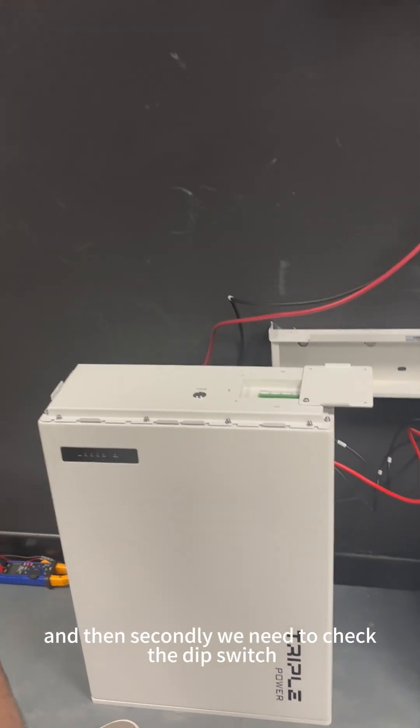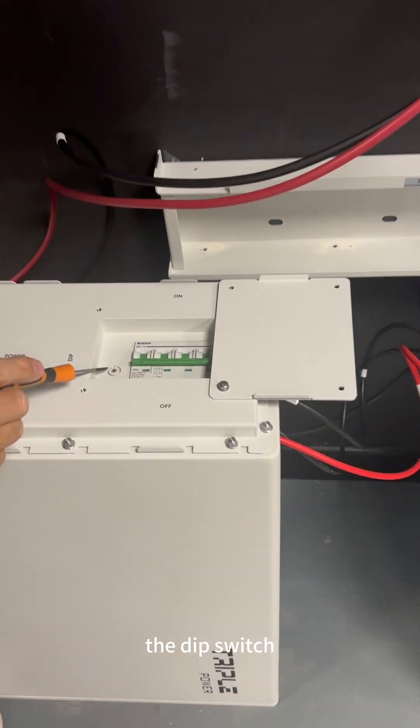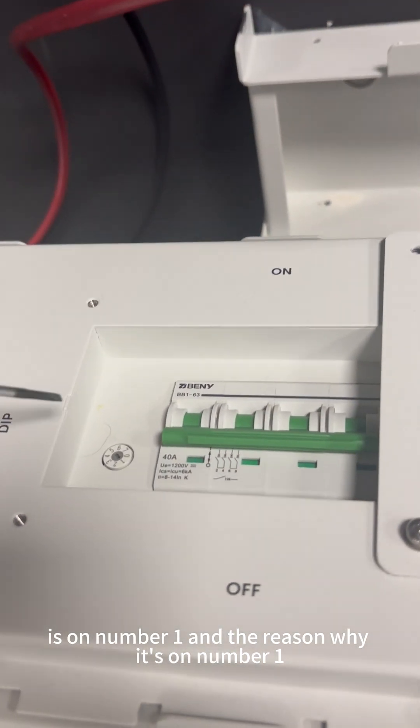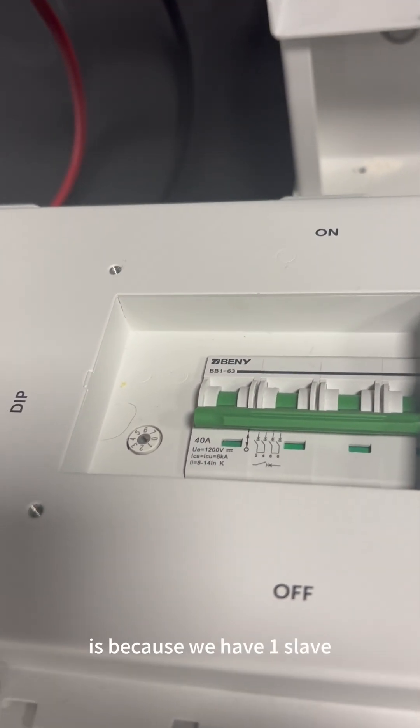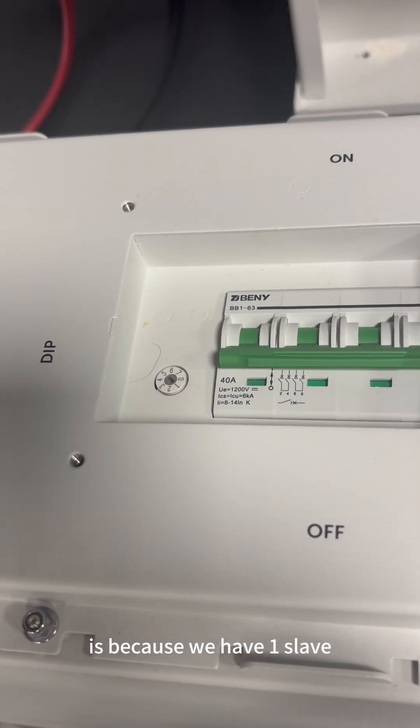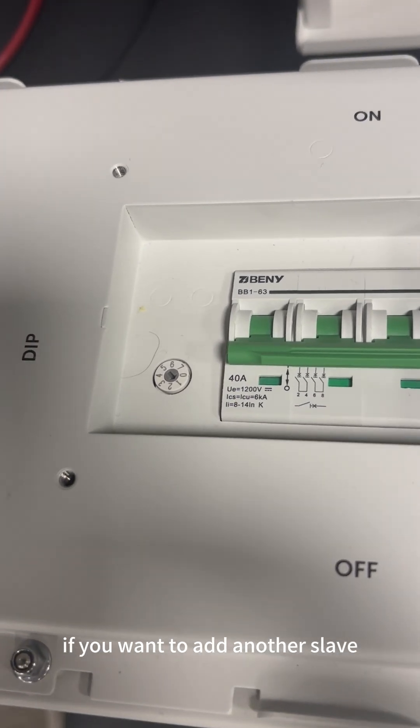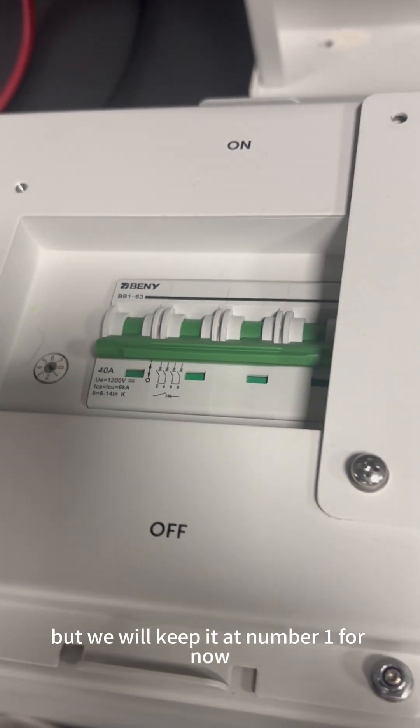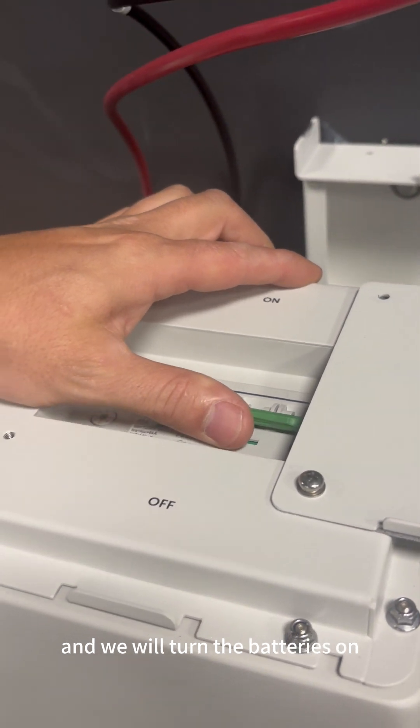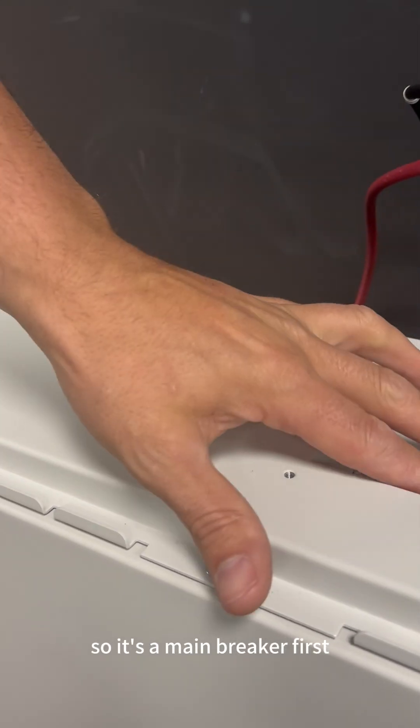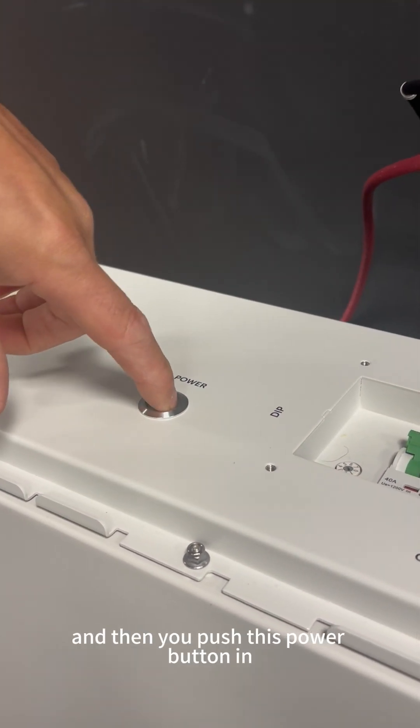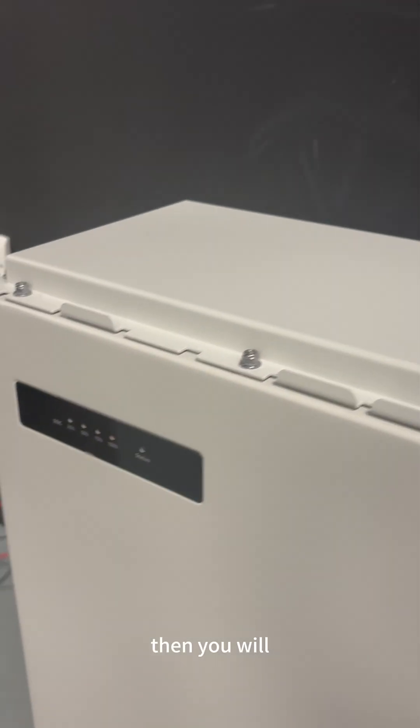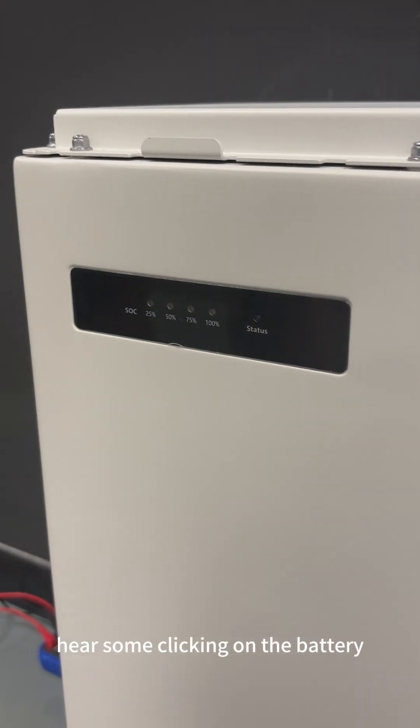The dip switch is on number one and the reason why it's on number one is because we have one slave. If you add another slave we need to change that to number two, but we will keep it at number one for now. We will turn the batteries on, so it's the main breaker first and then you push this power button in. Then you will hear some clicking on the battery and you'll see this light here flashing.